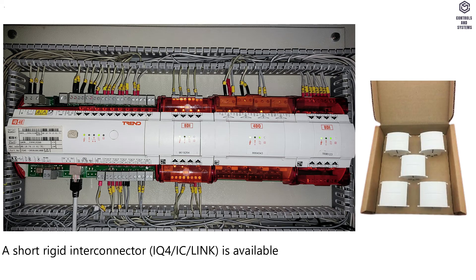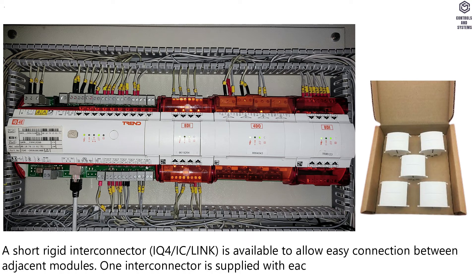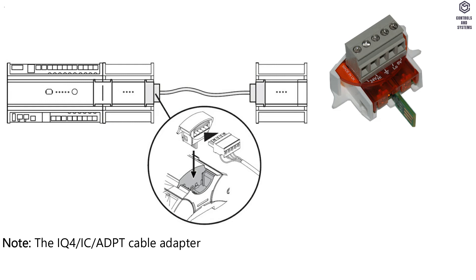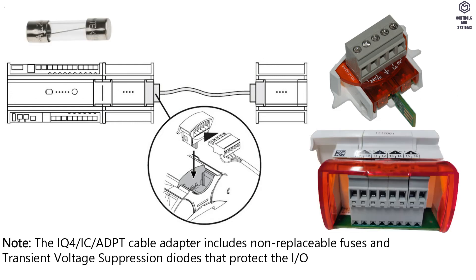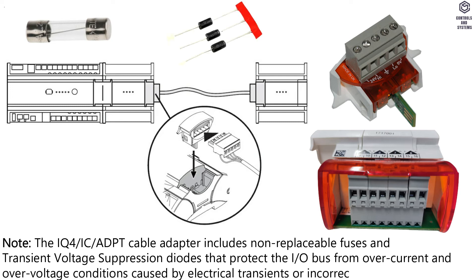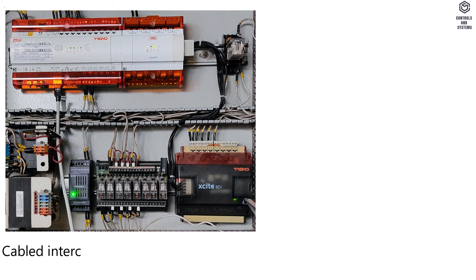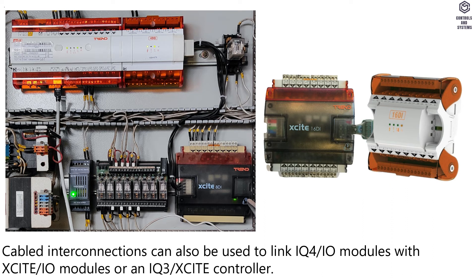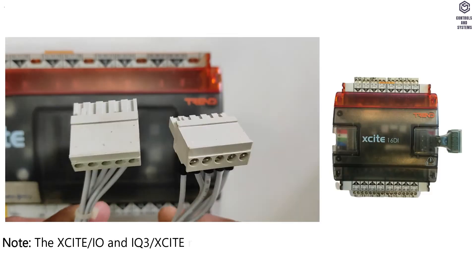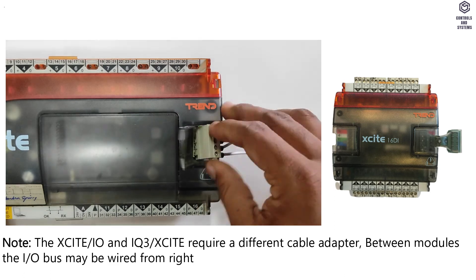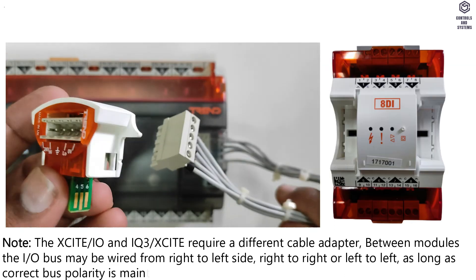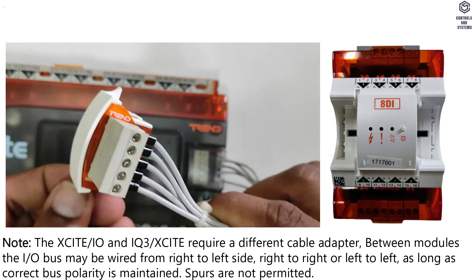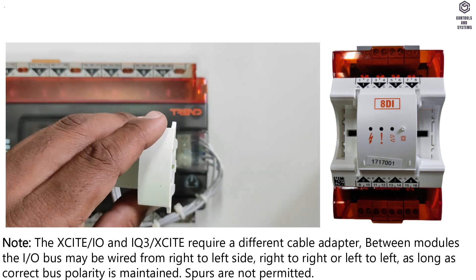A short rigid inter-connector (IQ4IC link) is available for easy connection between adjacent modules; one inter-connector is supplied with each I/O module. Note: the IQ4IC ADPT cable adapter includes non-replaceable fuses and transient voltage suppression diodes that protect the I/O bus from over-current and over-voltage conditions caused by electrical transients or incorrect wiring. Cabled interconnections can also link IQ4IO modules with XCITE I/O modules or an IQ3/XCITE controller; note that the XCITE I/O and IQ3/XCITE require a different cable adapter. Between modules, the I/O bus may be wired right to left, right to right, or left to left, as long as correct bus polarity is maintained. Spurs are not permitted.